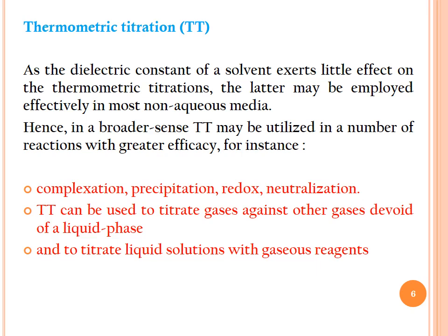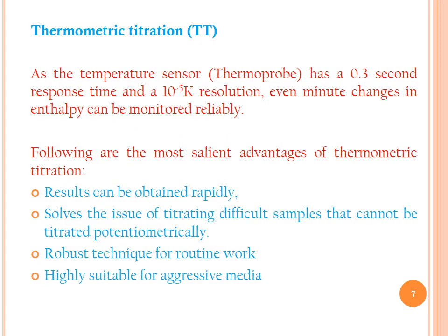TT can be used to titrate gas against other gases devoid of a liquid phase, and to titrate liquid solutions with gaseous reagents. As the temperature sensor, the thermoprobe, has a 0.3 second response time and a 10 raised to the power minus 5 Kelvin resolution, with high resolution titration even minute changes in enthalpy can be monitored reliably.